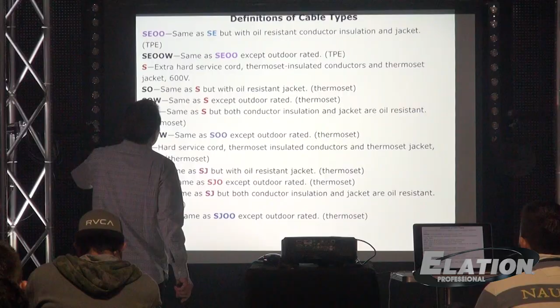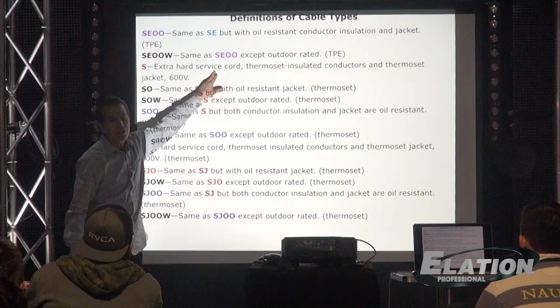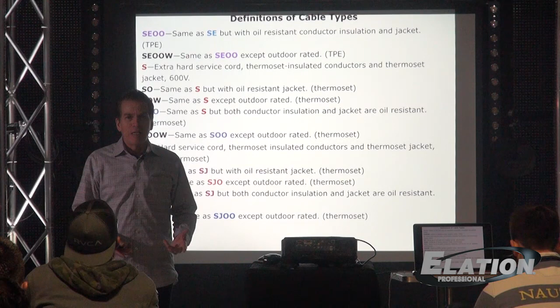And I mentioned that there are different cable types. This is just for your own use, definition of cable types. You'll see these designations a lot. Type S is extra hard usage cord or extra hard service cord. It's rated up to 600 volts. Cable has a voltage rating, just like it has an ampacity. Remember this morning we were talking about how water is kind of like electricity. So if you have a garden hose and you connect it to a fire hydrant that has a huge amount of pressure, and you had a nozzle to turn the water on and off, and if that garden hose tried to hold back all that pressure from a fire hydrant, it couldn't do it. It would spring a leak.